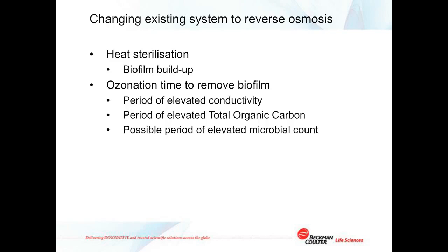When first applied, the ozone will start to break down the surface of the biofilm, oxidizing the organic materials to form carbon dioxide. And this carbon dioxide dissolves in the water and elevates the conductivity. So we're going to have spikes of TOC and elevated conductivity. Secondly, as the biofilm is broken down, organic material will slough off the inside of the pipe and elevate the TOC levels in the water.